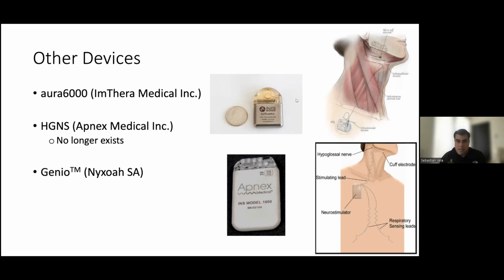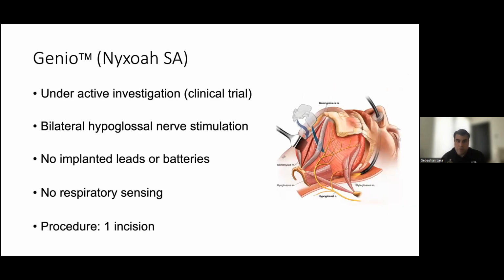And then the last that I haven't mentioned yet, but is under current active investigation, is the Genio by Nyxoah. So the Genio is different in a few ways. One is that it's a device that allows for bilateral hypoglossal nerve stimulation using bilateral padded electrodes. It doesn't have any implanted leads or batteries, and it doesn't have a respiratory sensor. And so as a result, this can be implanted using only 1 incision, which is in the submental region. And because it doesn't have an implanted battery, it doesn't need to undergo battery changes.